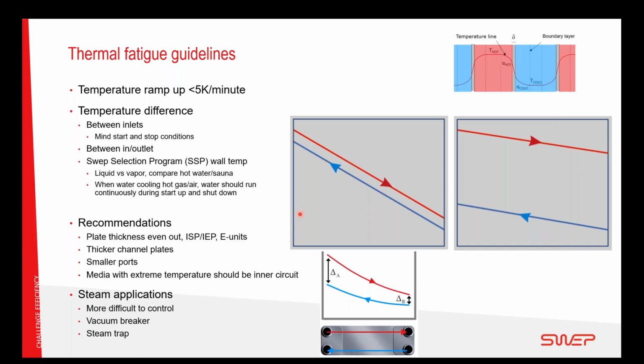thermal shock. Some recommendations that we have is that you should even out the plate thickness between the channel plates and the cover plates. That's, for example, also our E-units, which have the integrated start and end plates. That's a thinner cover plate. So we will lower the tension between the channel plates and the cover plates. They will then expand more at the same rate from the thermal expansion. Smaller ports will also make a stronger unit. And we should always have the media with the most extreme temperature on the inner circuit of the plate heat exchanger. We can also build the heat exchanger more thermally resistant by adding more isolating channels to the cover plates. That's also one way to increase the lifetime when it comes to thermal fatigue.